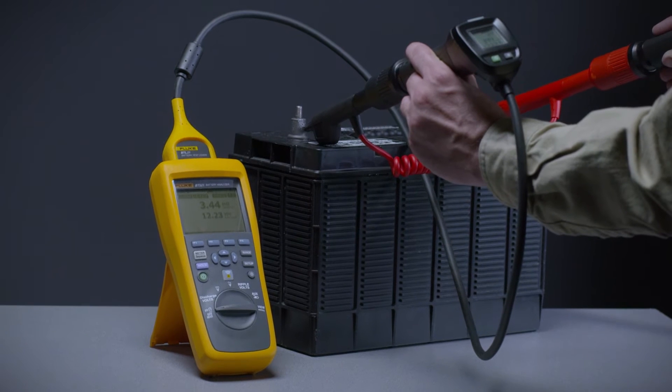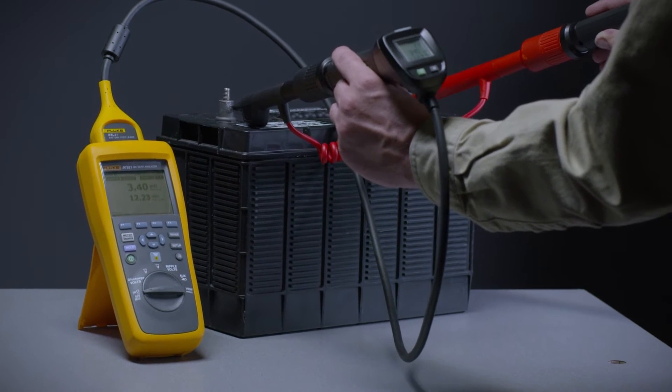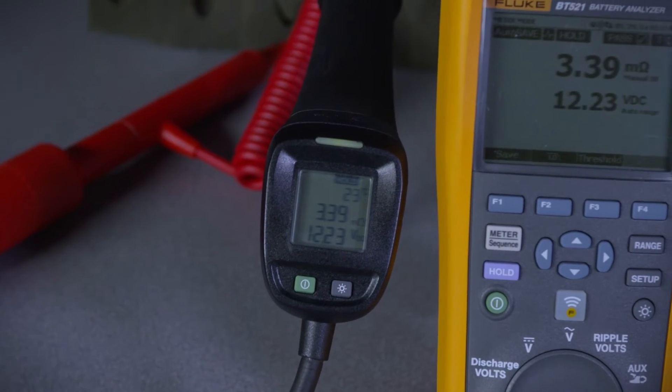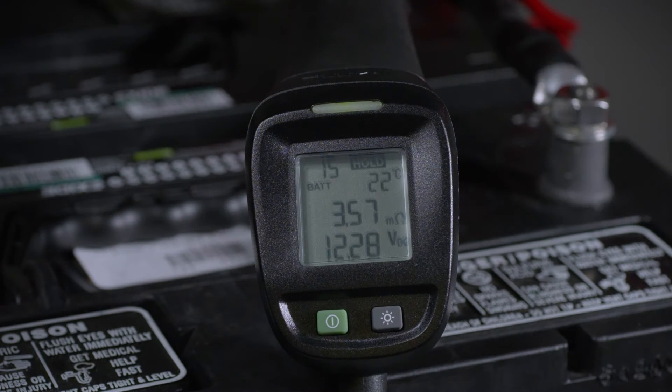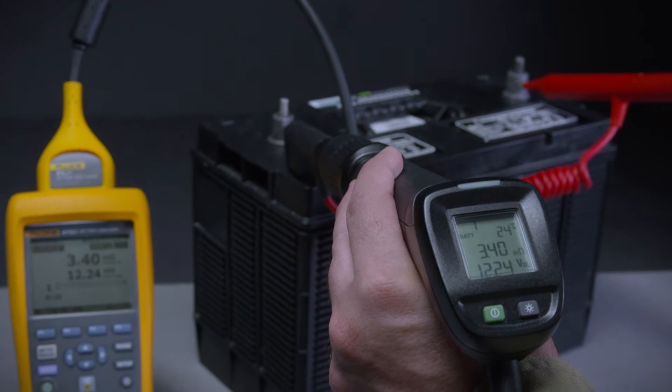One of the most significant improvements with the Fluke battery analyzer is the addition of intelligent test probes. The BTL21 intelligent test probe has the ability to indicate voltage as well as other readings such as milli-ohms and temperature right on the integrated LCD display, eliminating the need to refer to the main unit to verify measurement results.